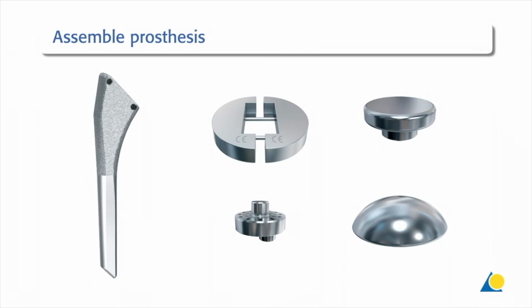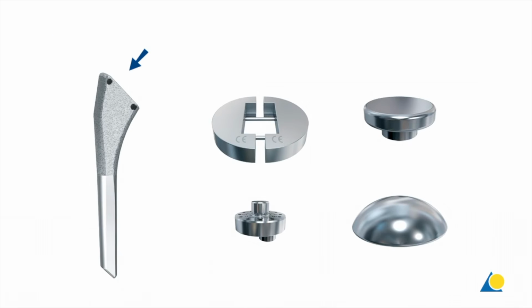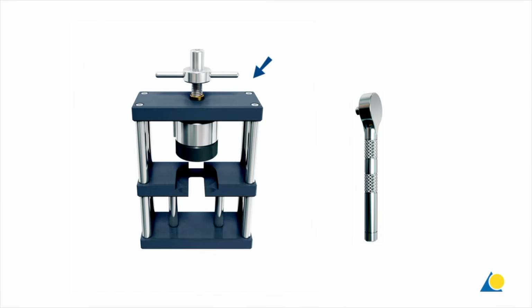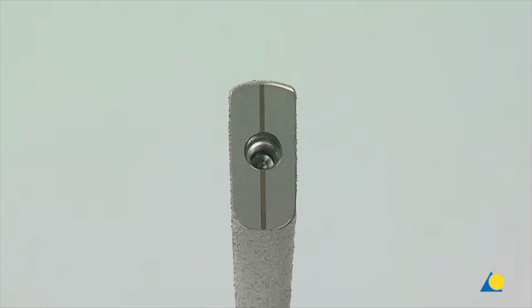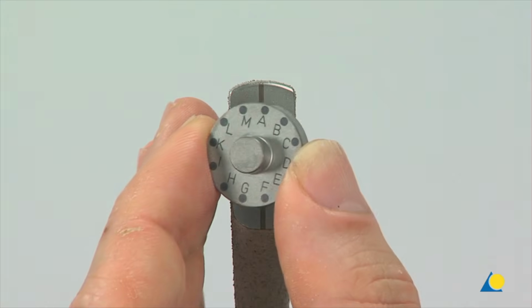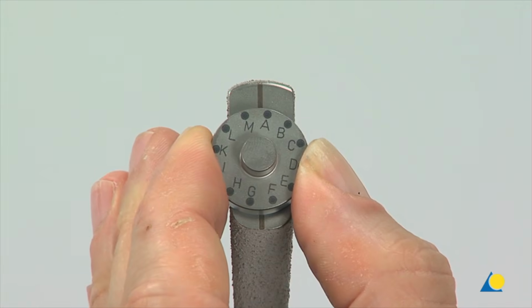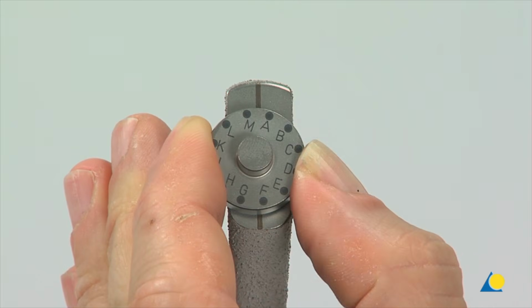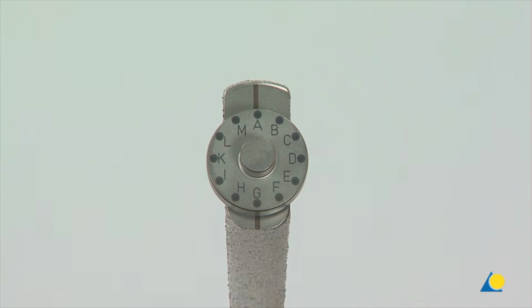To assemble the prosthesis, a humeral stem, a stem holder, an eccenter impactor, and a head are needed, along with a press and a torque wrench. The eccenter is positioned on the stem. The offset letter A that was noted during the trial implantation is aligned with the center line of the stem. The eccenter has to sit flush on the stem.